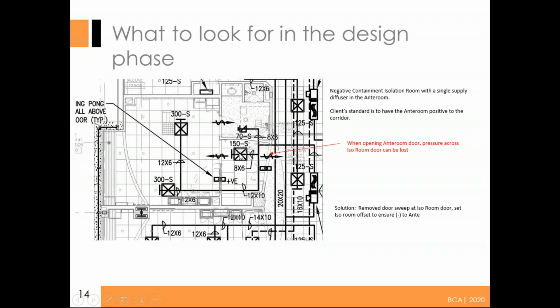So their typical design is one supply grill in the ante room. The one thing to keep in mind here is that in an isolation room, a negative room, we can make a negative room look negative across the door by either making a negative offset in this room or by making a positive offset in the adjacent room. So what can happen here with only a supply is this supply diffuser could actually be providing the major portion of the pressure pushing against the door.